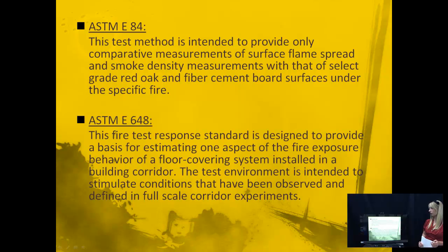ASTM E84 is a test method and is intended to provide only comparative measurements of surface flame spread and smoke density measurements with that of select grade red oak and fiber cement board surfaces under the specific fire.